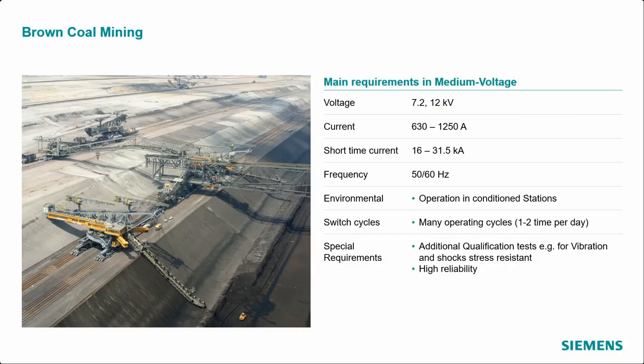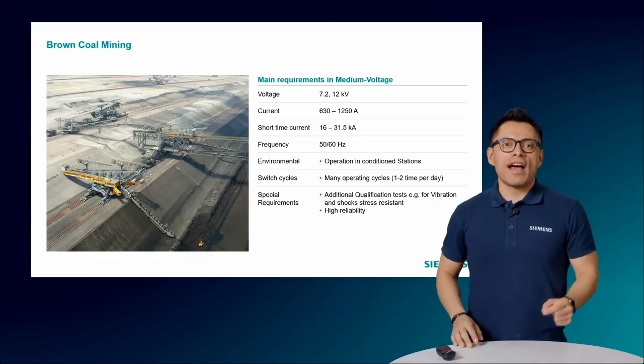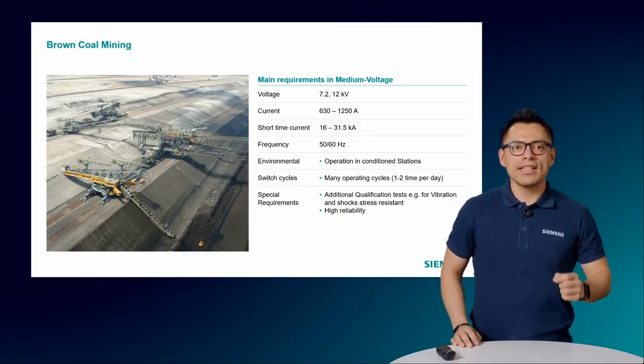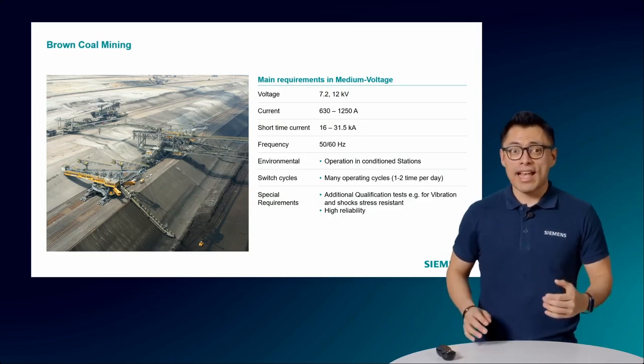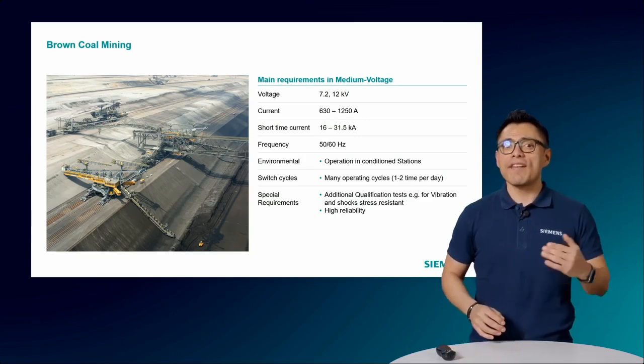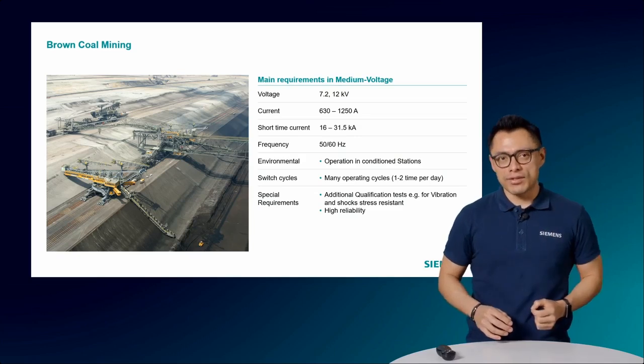Finally, another very interesting application is brown coal mining. For this application, the medium voltage switchgear needs to be installed in the large-scale excavator, and due to the strong and continuous vibration, the switchgear needs to have an additional qualification test for vibration and shock stress resistance. They also need to have a robust design to withstand the dusty and harsh mining environment, as well as a high power handling to support the heavy machinery used in mining operations.